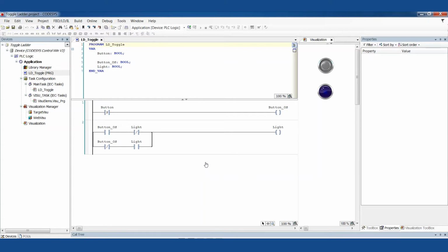Well, when I click this button here, even if I click it as quickly as I can, it's going to be on for some number of milliseconds. And for most PLCs, that's plenty of time for it to scan through all of the code several times. And that means if we're just looking to see if this is on and then saying, if this is on, then change state, we're going to end up changing state several times, even in that really quick click that I'm making, or that really quick push with my finger on a physical button.